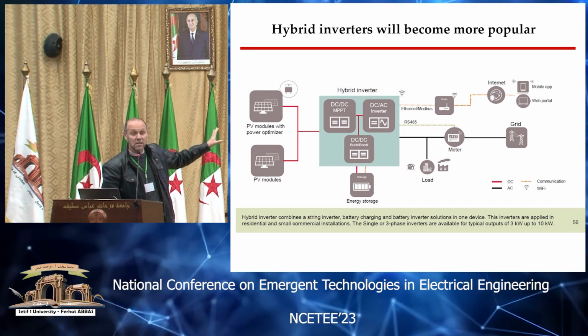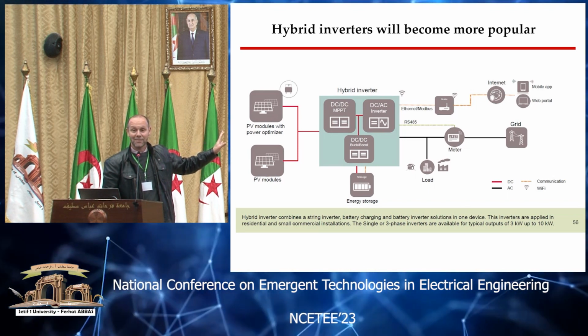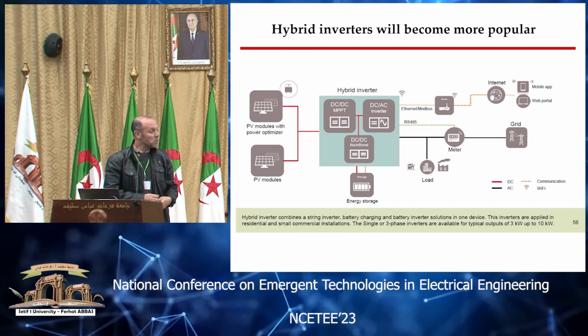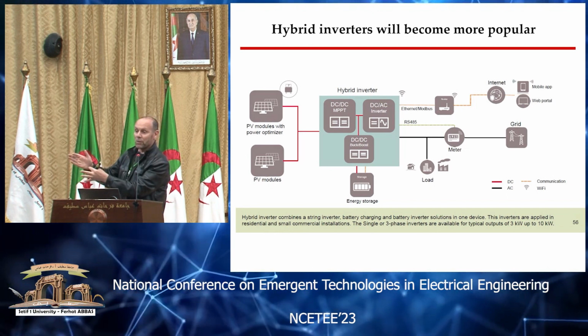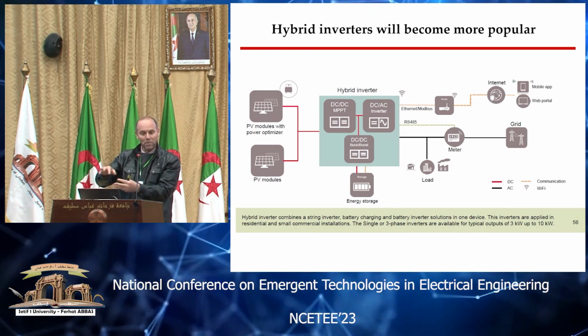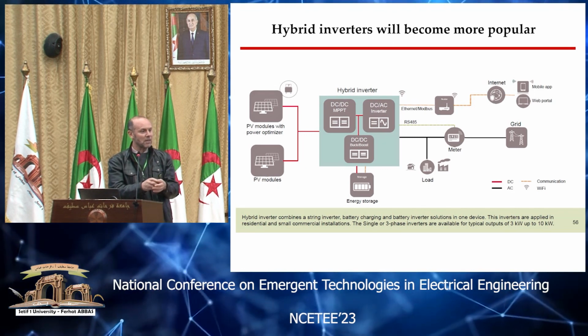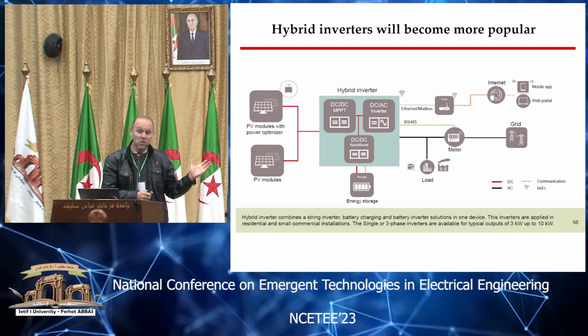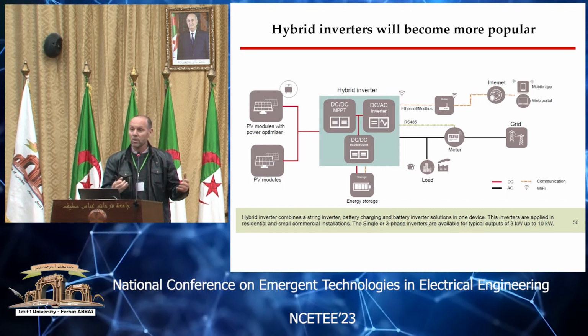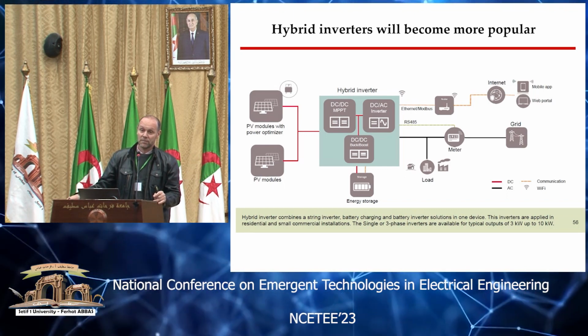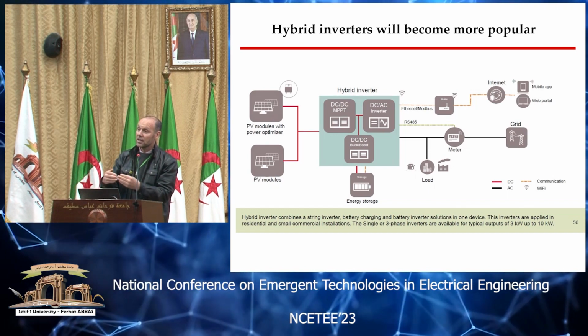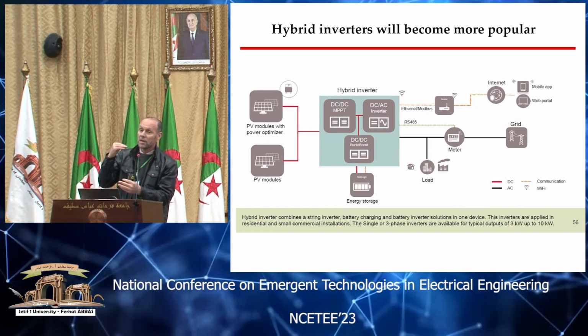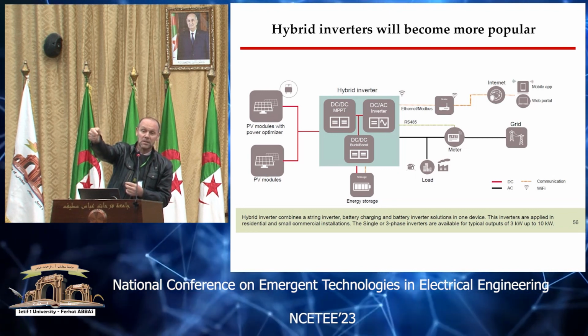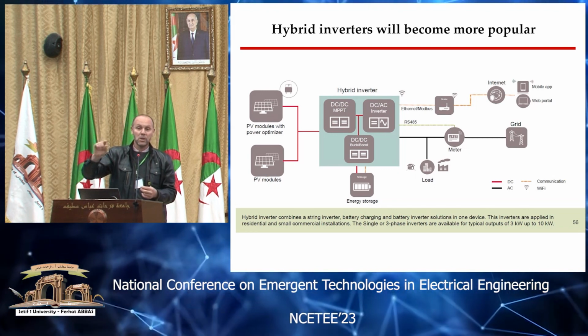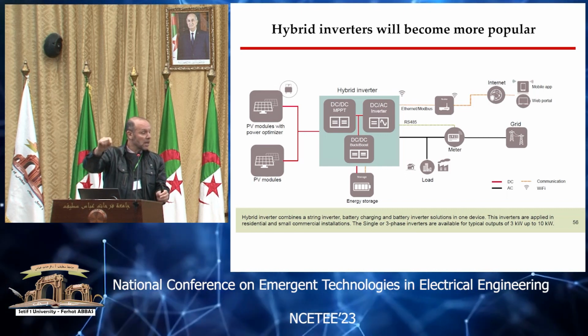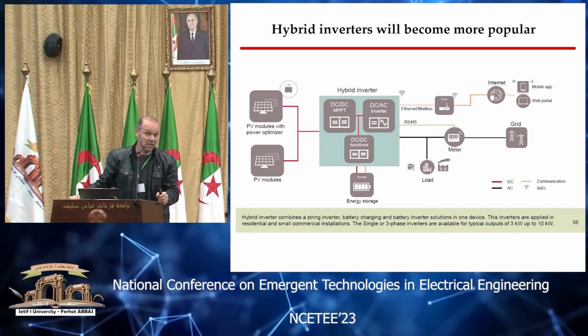Because previous inverters are grid-following. Grid-following means they follow the grid - we assume the grid has stable voltage, stable frequency, and we use a phase-locked loop as a reference to inject active and reactive power. But the new inverters - and this is also a very hot topic - are grid-forming inverters. This means the inverter should be able to help stabilize the frequency and voltage of the grid, connecting to any voltage, any frequency, and helping to stabilize the grid.